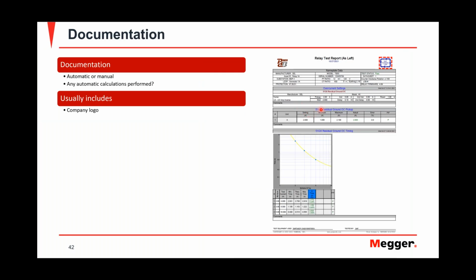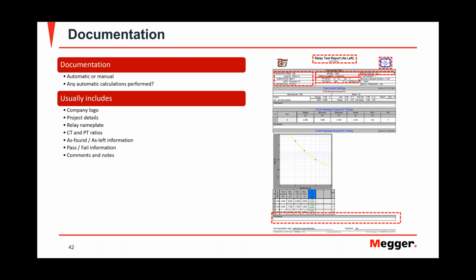Then they'll look into the report. But if they don't see that green pass, you're going to have some questions, and you better be prepared. Sometimes it boils down to knowing how to set up the boundary conditions. Some things that your documentation, in my opinion, should include: the company logo, the project details, the relay nameplate, CT-PT ratios. Is this as found or as left settings information or testing information? Obviously, whether it passes or fails, and some comments, notes.